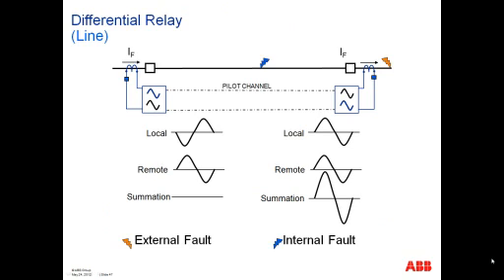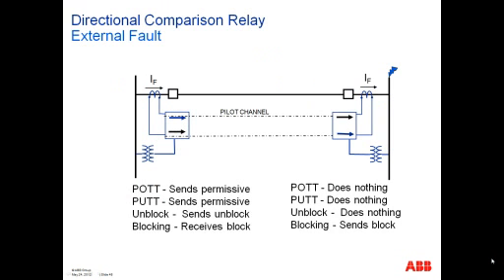Your line differential relay usually involves some type of digital channel to transmit the information. In older relays, it was actually a conductor. But anyway, you basically transmit the waveform from one end to the other, and at the local end where you're receiving the voltage or current information from the remote end, you compare the two quantities to determine whether it's internal or external. Of course, for an external fault, the summation of the two quantities would be 0, and for an internal fault, there would be some value there.